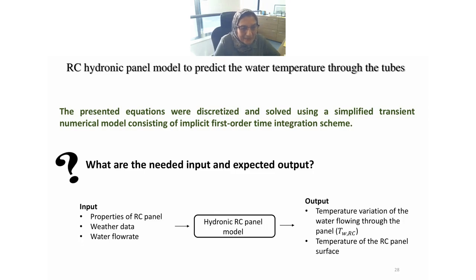Using the hydronic panel model, I get as output the temperature variation of the water flow through the panel in the direction of flow, and the temperature of the radiative cooling panel surface. So I have both the panel surface temperature and the water temperature.